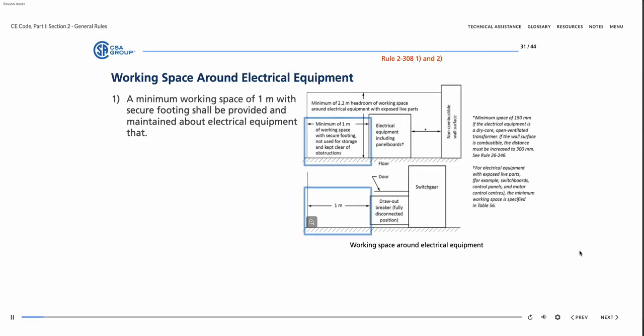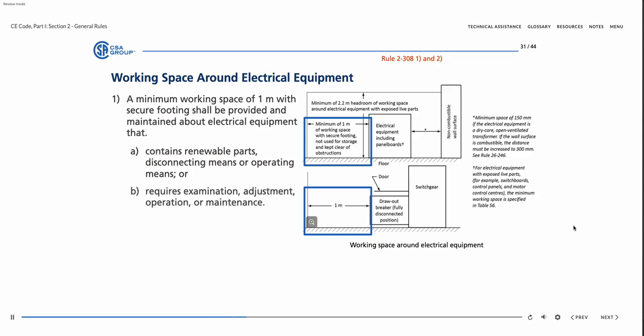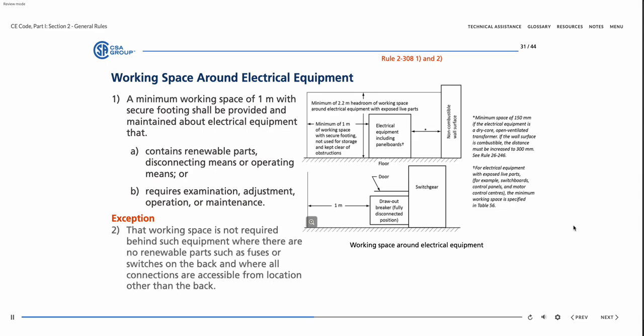A minimum working space of 1 meter with secure footing shall be provided and maintained about electrical equipment that contains renewable parts, disconnecting means or operating means, or requires examination, adjustment, operation, or maintenance. An exception to this rule indicates that working space is not required behind such equipment, where there are no renewable parts such as fuses or switches on the back, and where all connections are accessible from locations other than the back.